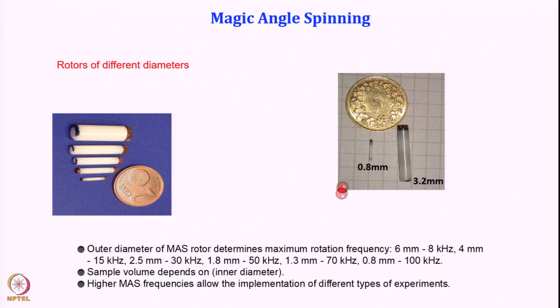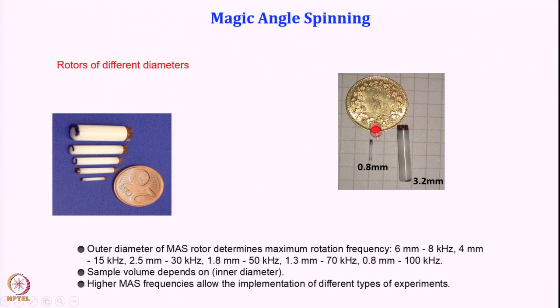As we miniaturize the rotor size, the sample that we can pack inside is also going to be very small. Sample volume depends on the inner diameter of the rotor. The material must be very stable, which is why it is made of zirconium oxide. There is a top cap with fins that drives the spinning. Smaller size means faster rotation, and bigger size means slower rotation. This also determines what kind of experiments we can implement. When spinning fast we can average out stronger interactions.